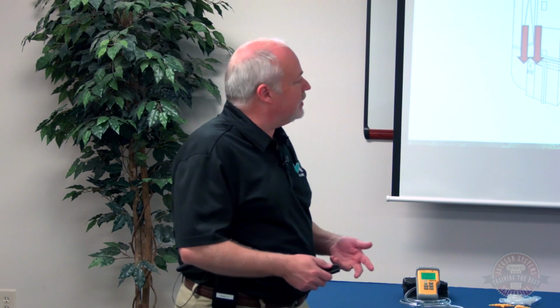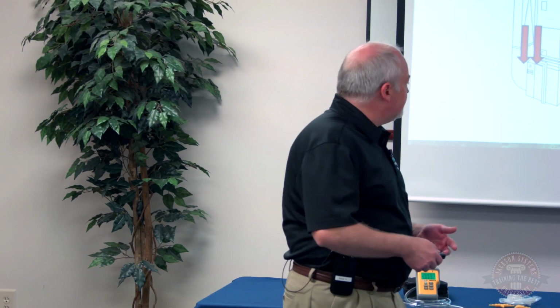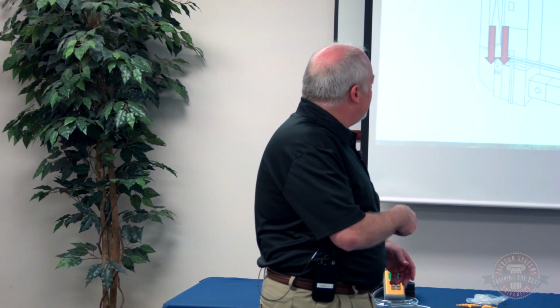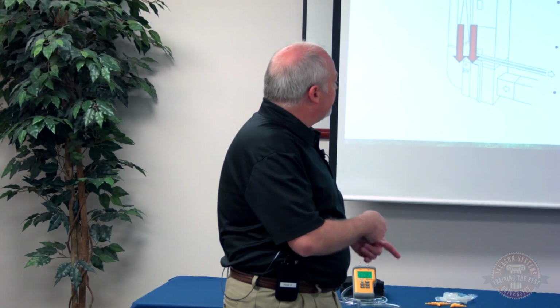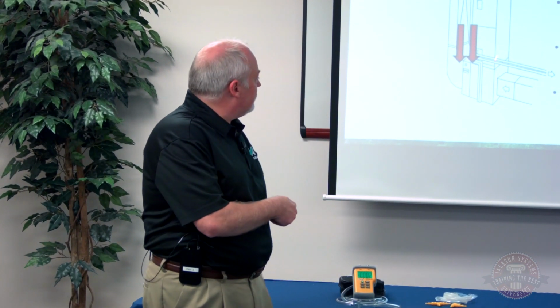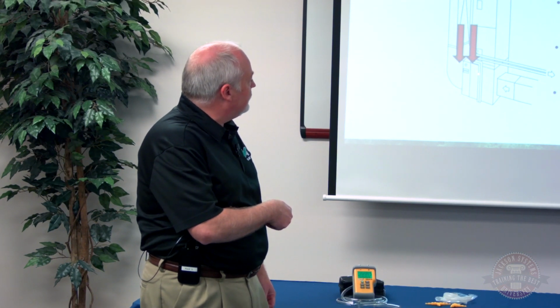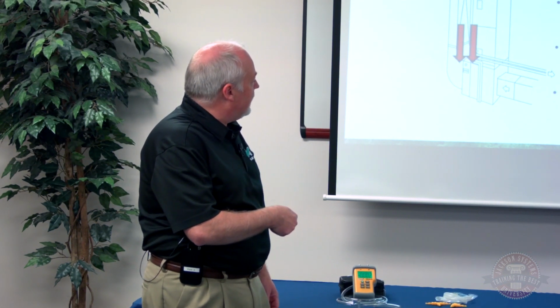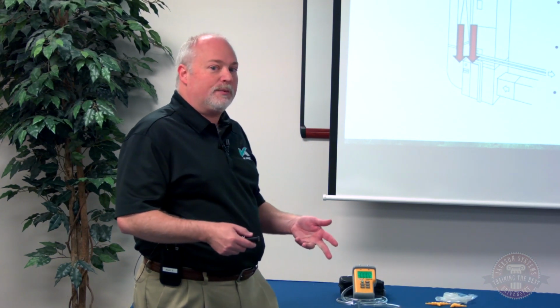So we take that example and we find that, hey, I've got too high of a temperature rise, I don't have enough airflow, how can I figure out where my issue is? Well, a while ago when we were checking our total external static pressure, we wanted to eliminate the filter and the coil from that. Now, when we're trying to solve our issue, let's take a look at what our pressure drop is across our filter. We want to look at the two different sides. So let's say I've got 0.11 on one side of this and 0.21 on the other. I'm going to subtract that and come up with 1/10 of an inch pressure drop across my filter, which is typically what we would want to see: 1/10 of an inch or less pressure drop across that filter.